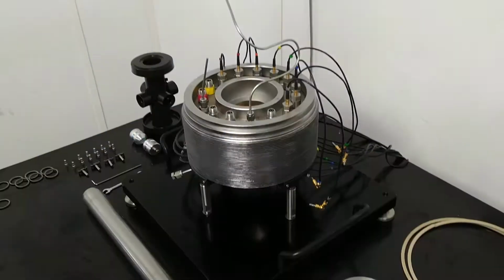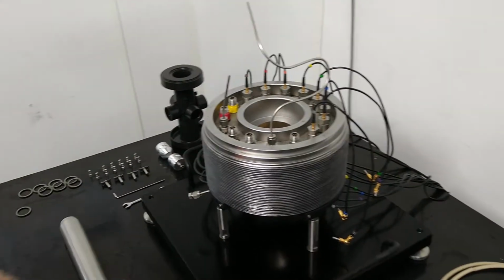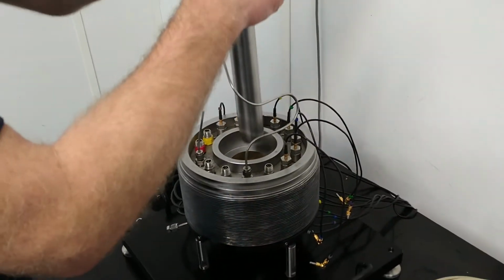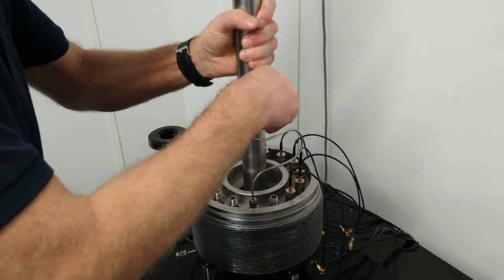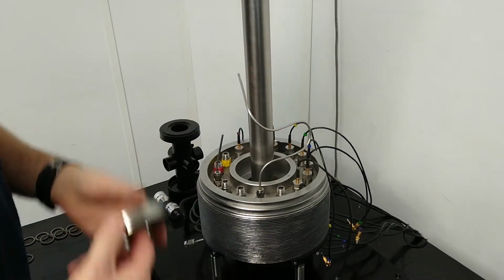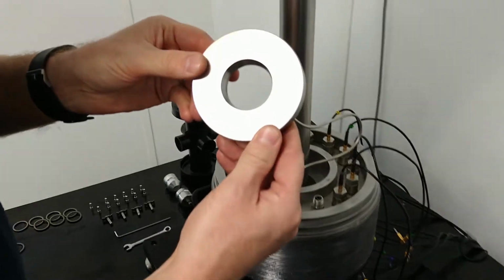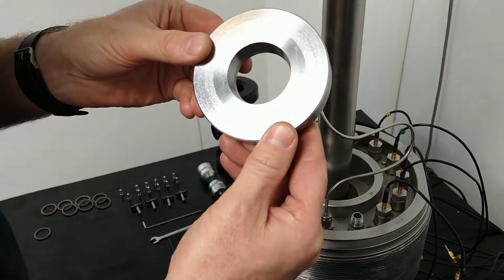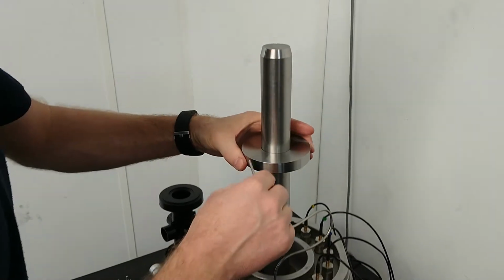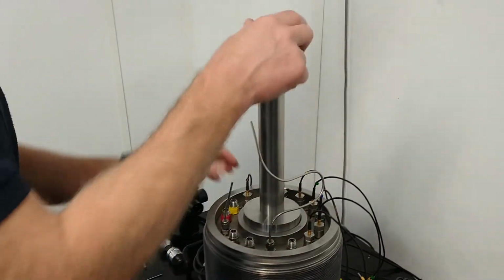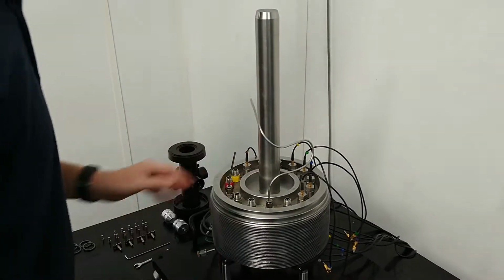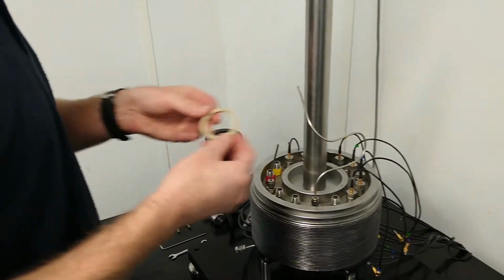To start assembling the internal components of the cell, ensure the cell base is securely located on the assembly jig. Place the assembly aid through the center of the cell base until touching the assembly jig. Place one of the two sample spacer rings down the assembly aid, with the chamfered edge facing downwards. No force should be required to fully locate the ring into the cell base.